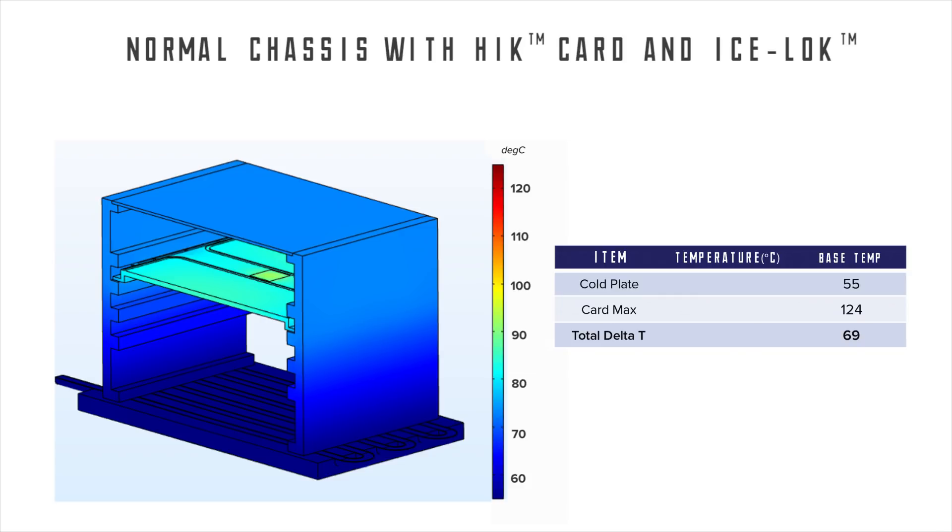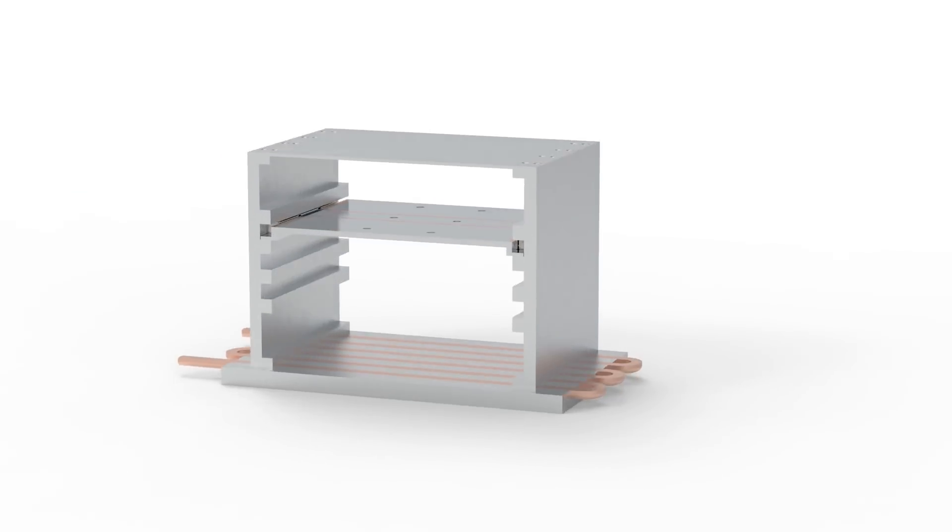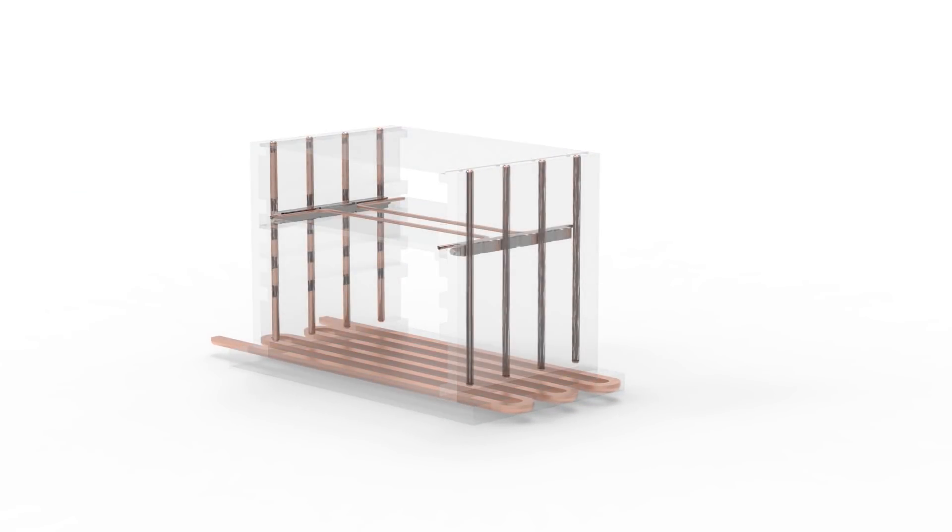The card max temperature is now 92 degrees C, which is a total delta T of 37 degrees C. With these two minor changes, neither of which significantly affects geometry or weight, the system operates over 30 degrees cooler than the baseline model.